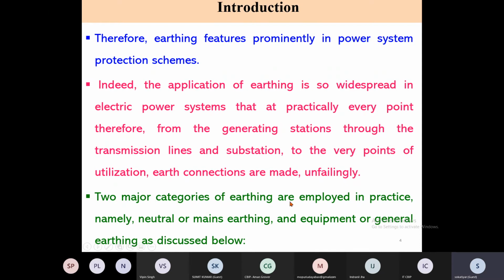Two major categories of earthing are employed in practice, namely neutral or mains earthing and body earthing. First, the neutral of the power equipment is grounded, that is the copper, and the body of the electrical equipment is grounded. So there are two types of grounding system. One is the body earthing, and another is that the neutral of the generator, of the transformer, or of the star connected motor has to be connected to the ground.